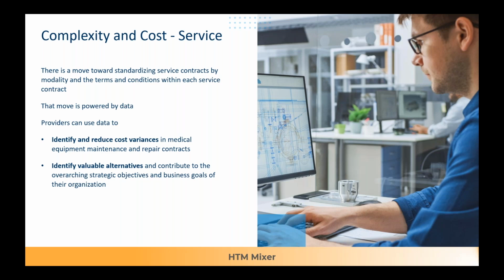When I was working up in Columbus at Nationwide Children's Hospital, we found that a clinic that was closed on the weekends, open Monday through Friday, 8 to 5, had a platinum level service contract on some of their equipment, which was 24-hour response time, nights and weekends and all this stuff, but they would never need that. They just liked that platinum agreement. They thought it was the best service. We were able to downgrade them to a gold agreement because we still needed that outside service, but we saved a substantial amount of money by evaluating that based on location and criticality.